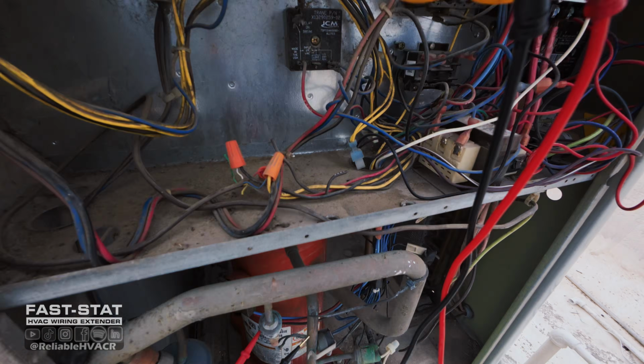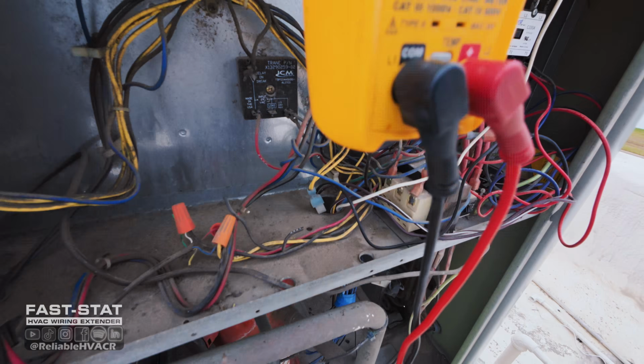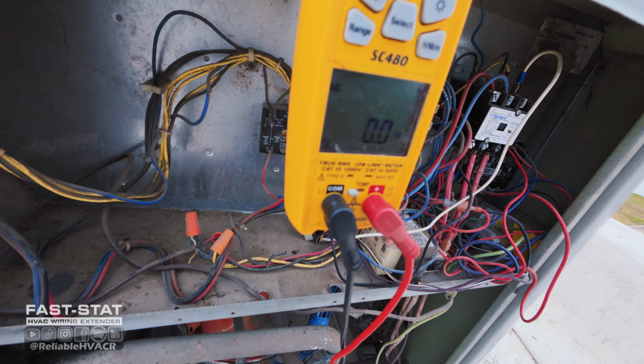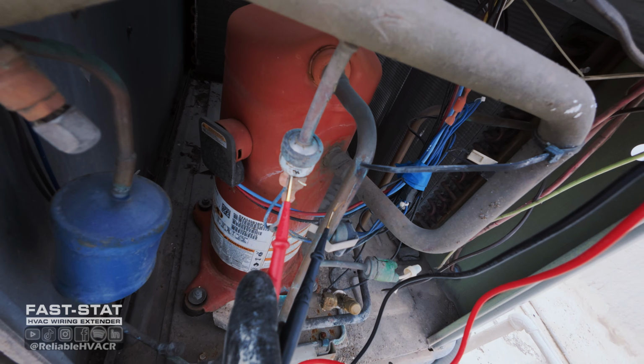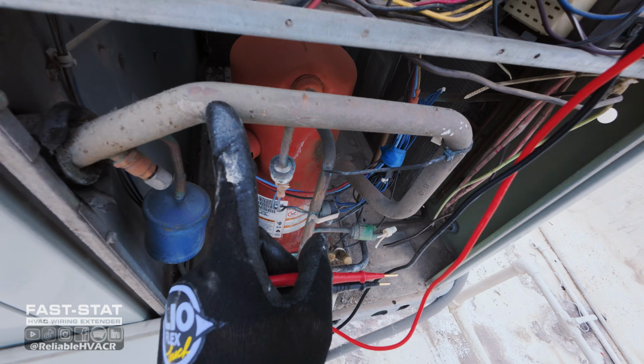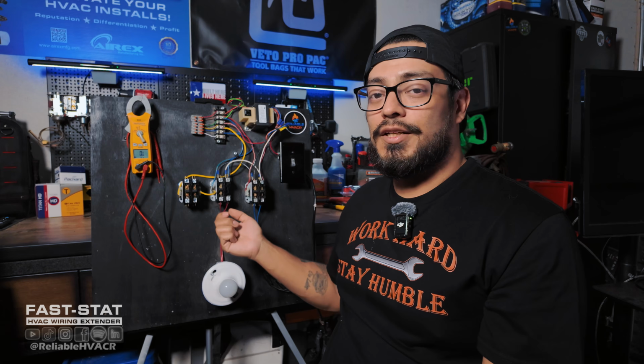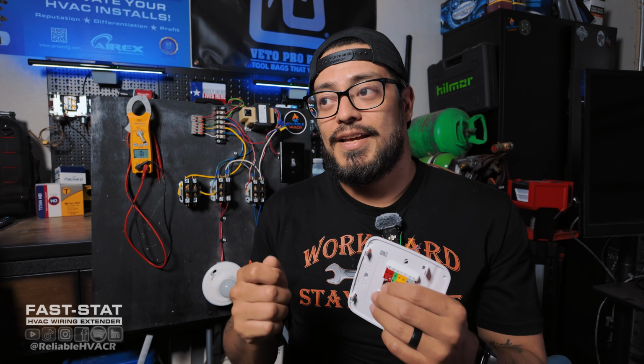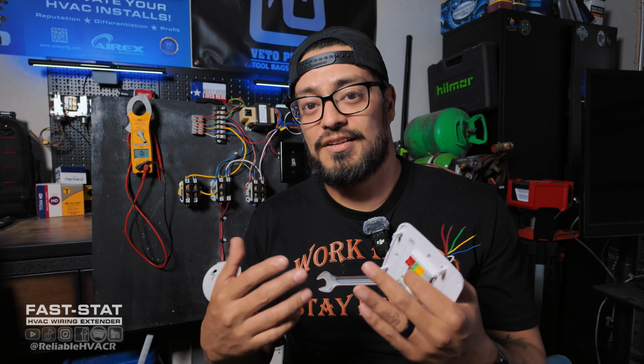On RTUs, and I think on residential, you're going to start seeing it more often, it's safeties. If you have a low pressure, high pressure safety switch, peanut style or whatever it is, they're usually in line with your contactor. So if you're still not getting 24 volts here at the coil, then you need to start also checking those pressure switches. All you're going to do is check across. If there is no voltage, you're good. If there's a tone, if you want to check it that way, you're good. Or no resistance, you're good.